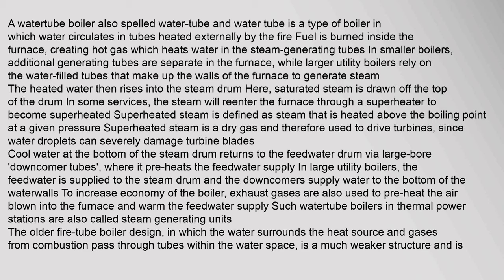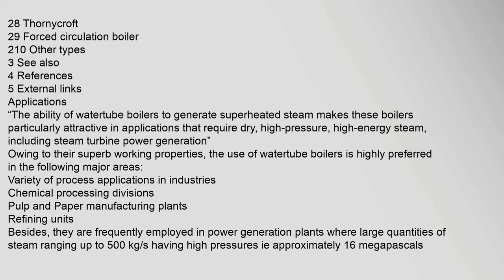Exhaust gases are also used to preheat the air blown into the furnace and warm the feedwater supply. Such water tube boilers in thermal power stations are also called steam generating units. The older fire tube boiler design, in which the water surrounds the heat source and gases from combustion pass through tubes within the water space, is a much weaker structure and is rarely used for high pressures.